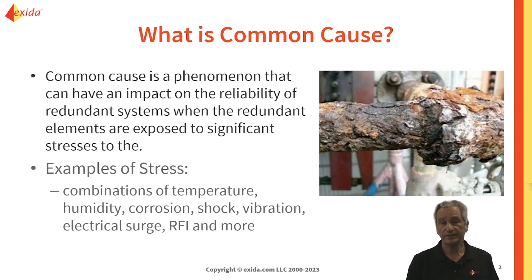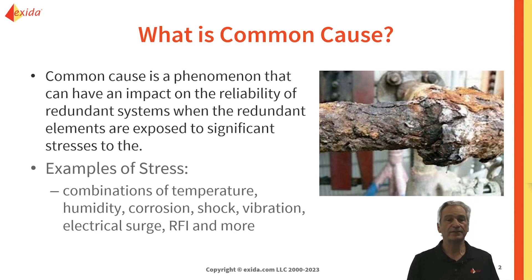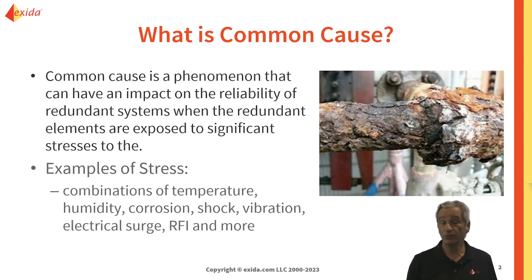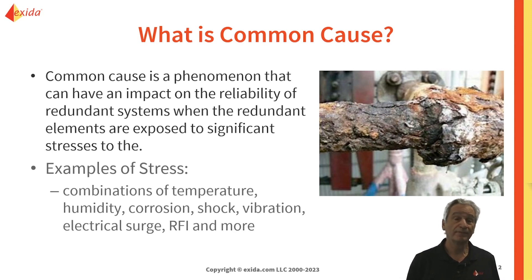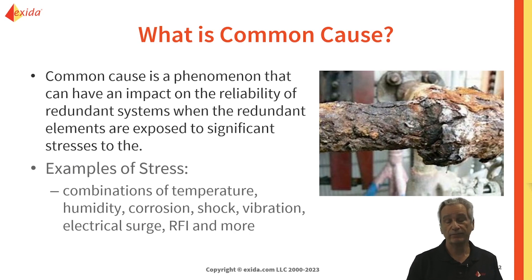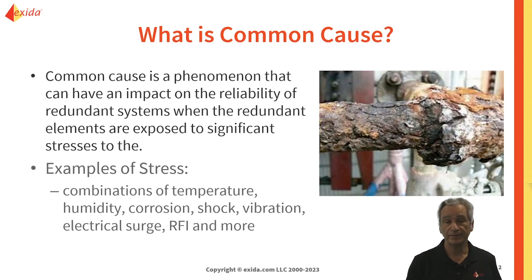Combinations of these stresses can be quite significant, but there can be other things as well. For example, a software bug. If we have the same controllers from the same manufacturer that have the same firmware or software, then that is an example of where a common cause — if there's a bug — could affect both systems.